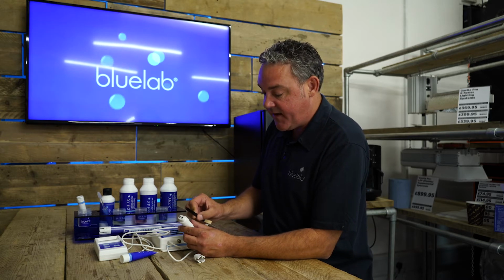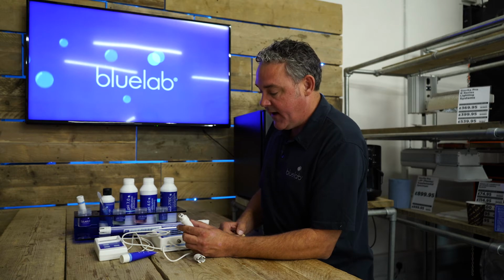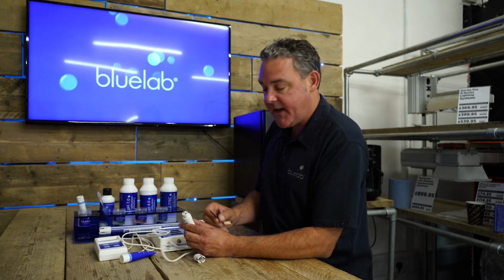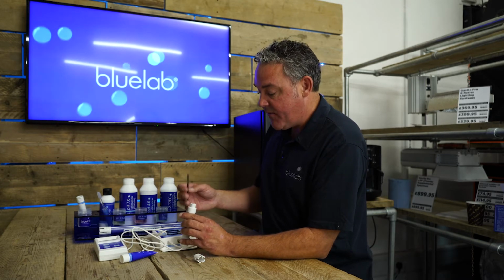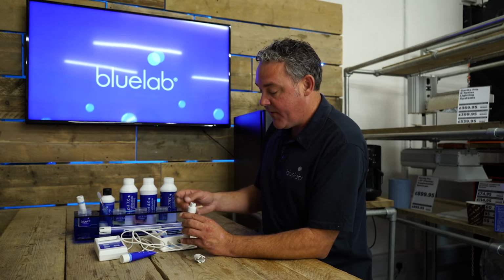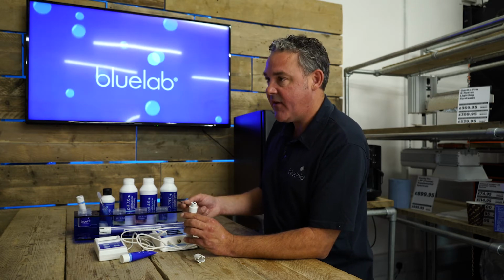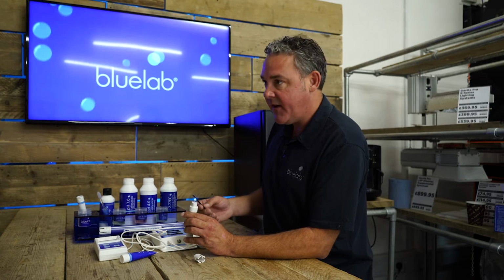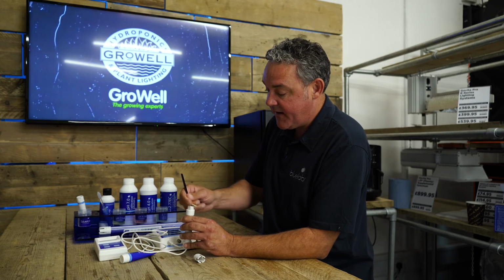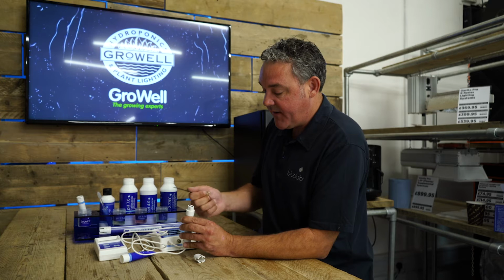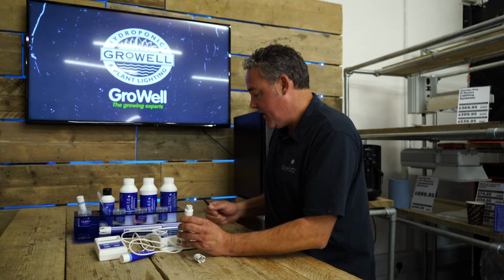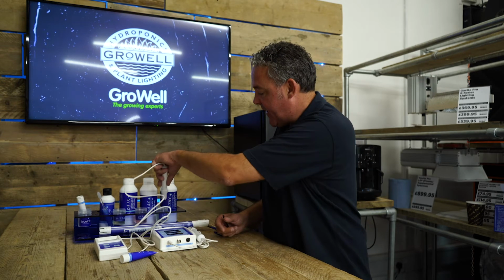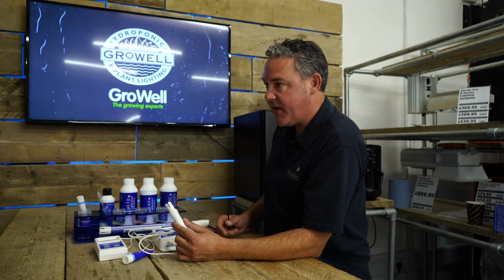All other EC meters I've seen have 2 metal prongs. Those prongs, it's almost impossible to clean. So what you're doing when you calibrate is you're really calibrating in the dirt, the reduced surface area of the sensor caused by it being dirty. But with ours, you just keep it clean. You clean it right back off. It essentially restores it to factory default. You put the shroud back on, test it in the 2.77, and you're good to go.